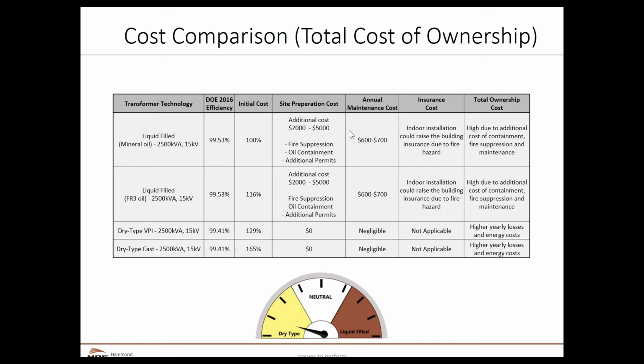Dry type transformers will have higher losses. So again, we'll have a little more electrical costs, but then things like insurance, testing, and maintenance might be lower with a dry type. So again, where the advantage would lie between the two designs, you can't make a blanket statement that says one is better than the other in all cases. You really have to look at the overall application where it's installed. However, especially if you talk about interior designs, a lot of times a dry type transformer will have some additional cost of ownership advantages over a liquid filled.